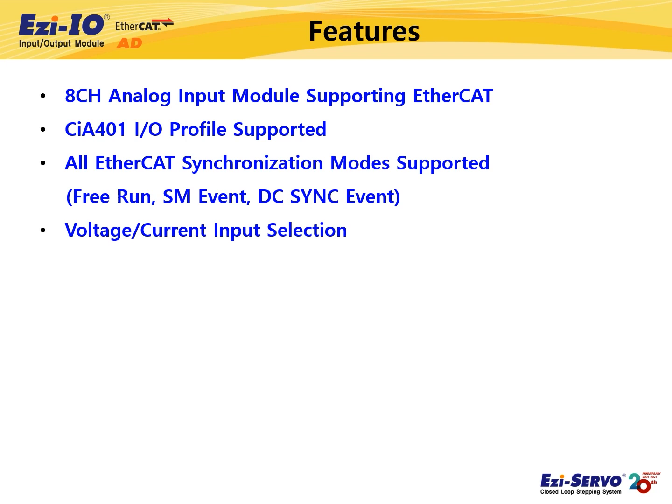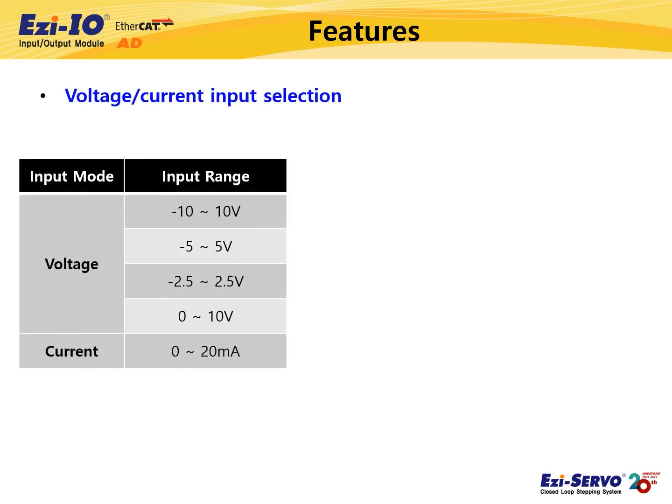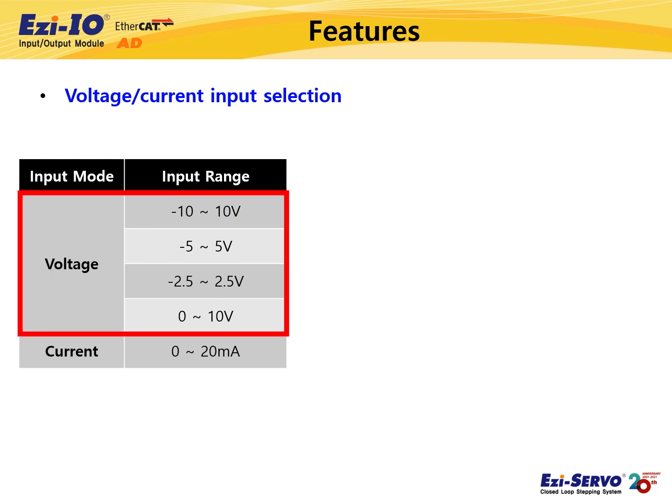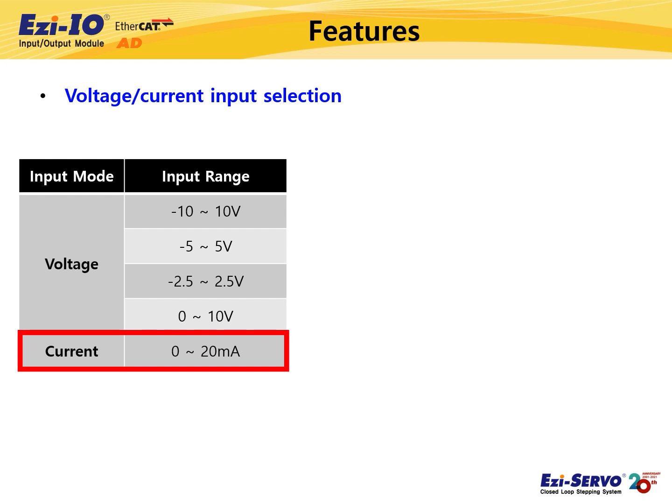Ezi-IO EtherCAT-AD supports voltage or current input mode — five input modes in total. For voltage input mode, there are four settings: minus 10 to 10 volts, minus 5 to 5 volts, minus 2.5 to 2.5 volts, and 0 to 10 volts. For current input mode, the input range is 0 to 20 milliamperes.